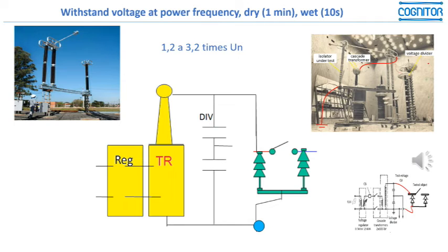Here you see the main concepts for the withstand voltage and power frequency dry and wet test. Usually it is a test in which you mount the equipment basically in the same way that it will be mounted in the substation, as far as possible. You feed the points where the insulation shall work properly under the specified voltage levels, and supply this voltage with one AC transformer.